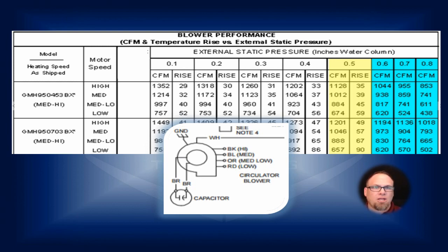Now think about it. You've got 0.8 inches of static on your high speed. Chances are going from high to medium, you're going to be probably somewhere closer or in between the 0.7 and 0.8. Okay, so let's say it drops down to 0.7. Well, check that out. At 0.8 on high speed, it was 853 CFM, but at 0.7 on medium speed, it's 859. It's actually 6 CFM higher on medium speed because of the change in the resistance in the ductwork.